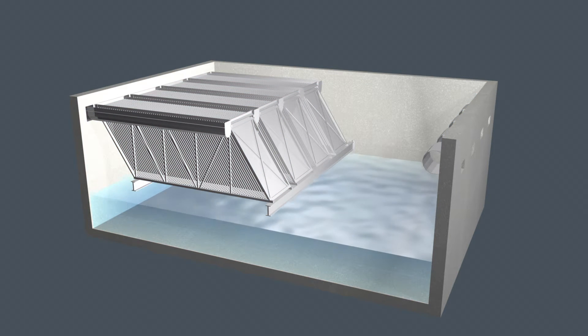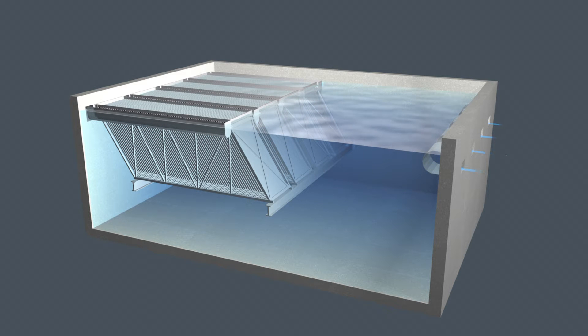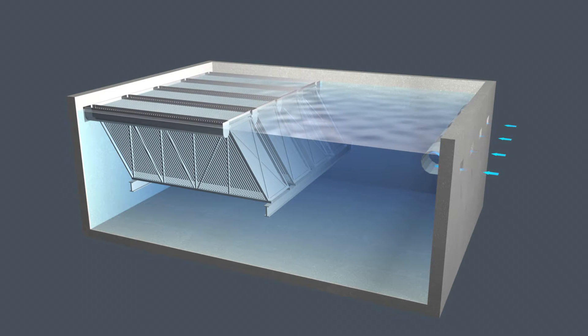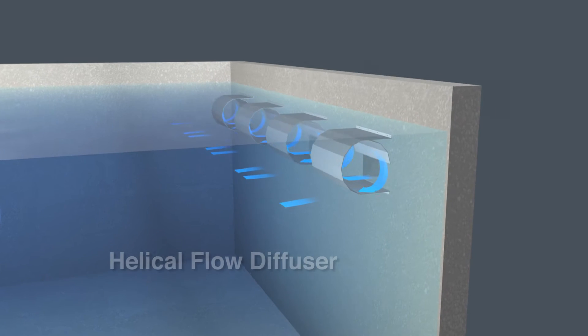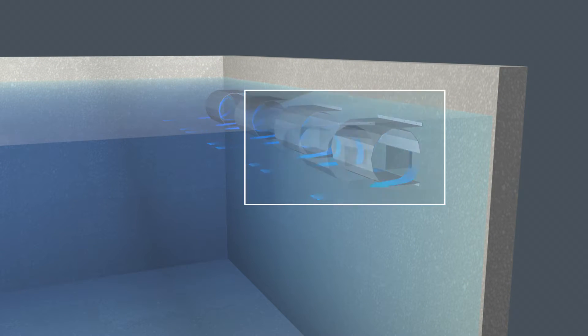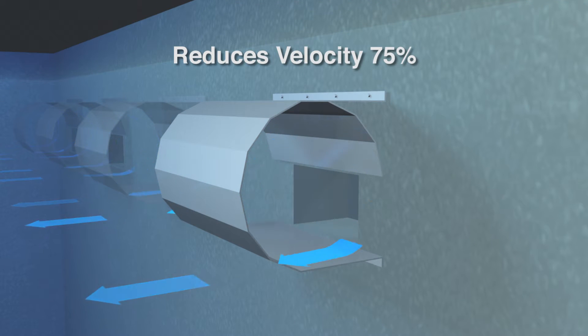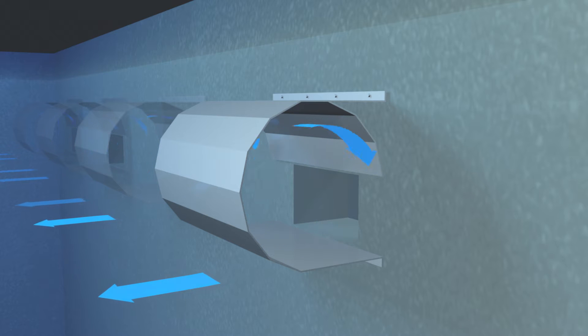Flow management begins when untreated water enters the sedimentation basin. The influent immediately passes through MRI's patented helical flow diffuser, which splits the flow and creates a rotating motion. This slows the velocity of the influent by 75% and protects the floc structure.